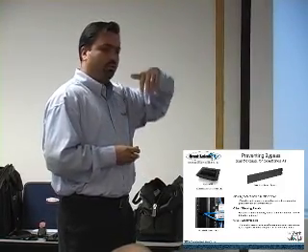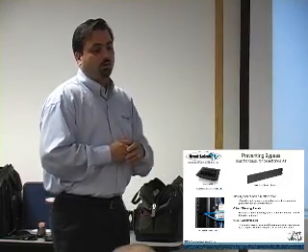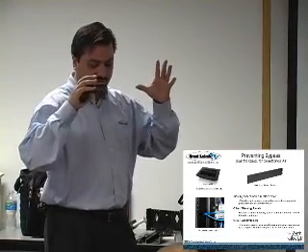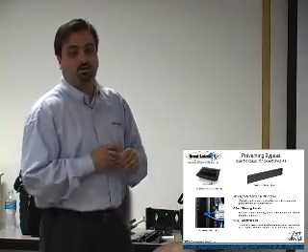We put sealant everywhere, inside the top of the cabinet, around the rails themselves, even in the bottom of the enclosure as well. We've seen some enclosures where you can actually eliminate the casters and levelers and seal the cabinet over the raised tile. That's your intake that way, so you don't have to actually pull the air through.